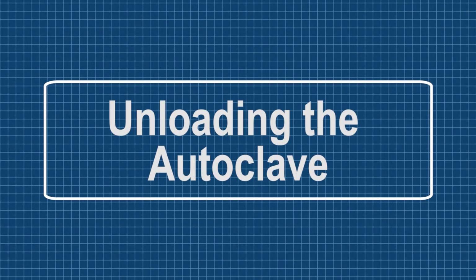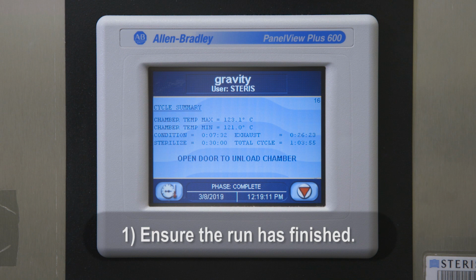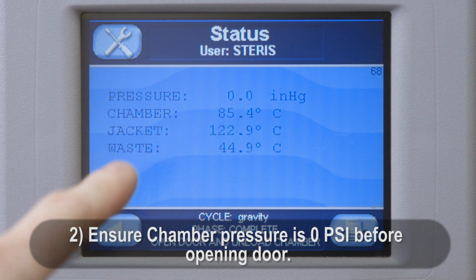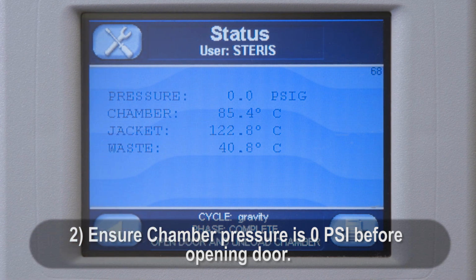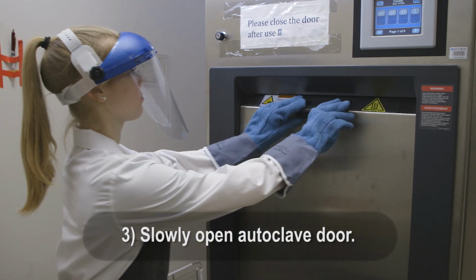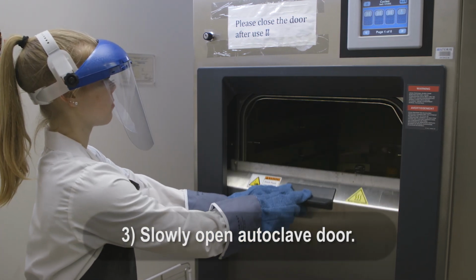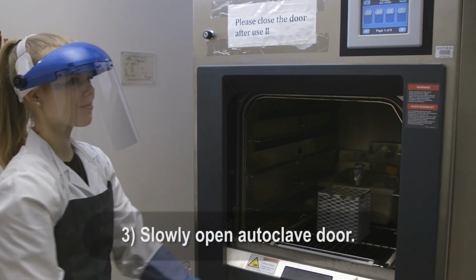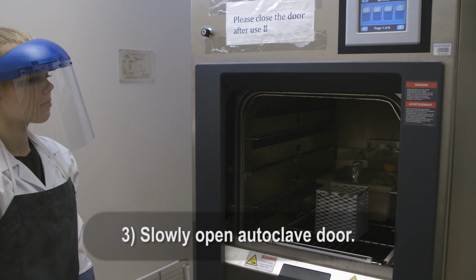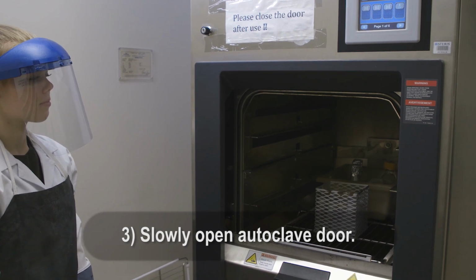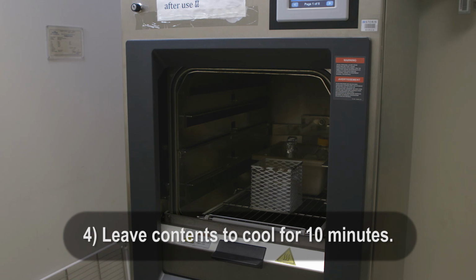After the autoclave has finished its run, follow these steps to safely retrieve your load. 1. Ensure that the run is finished. 2. Ensure that the pressure within the chamber is 0 psi before opening the door. 3. Slowly open the door to release residual steam and allow pressure within liquids and containers to normalize. Hot steam will exit the autoclave upon opening the door, so be careful. 4. After the door is open, leave the contents for 10 minutes to start cooling.